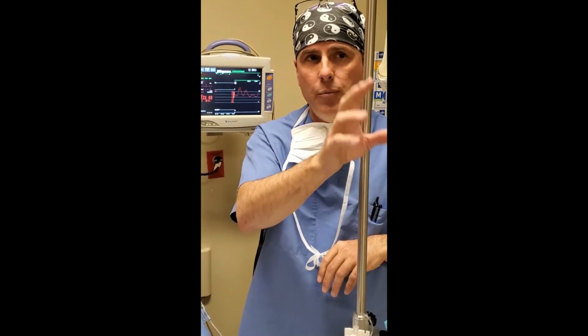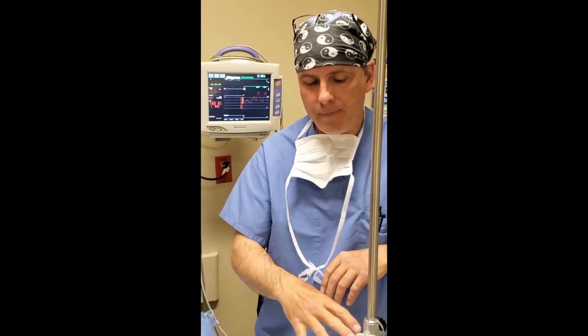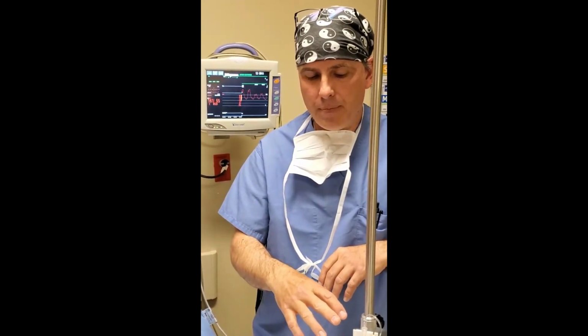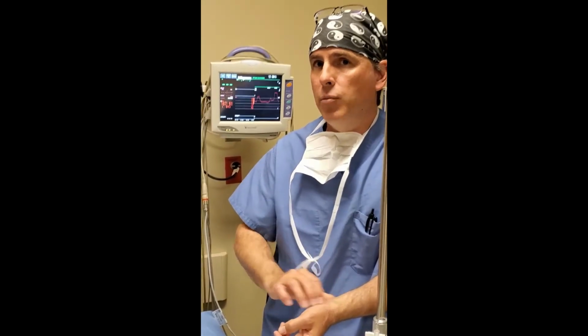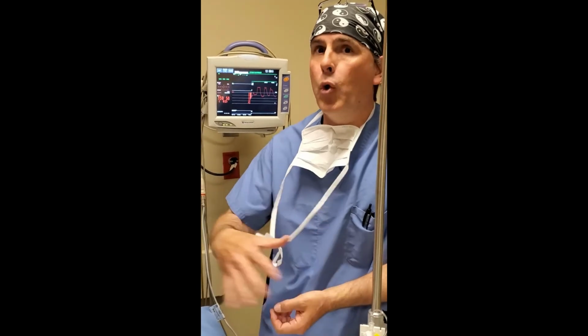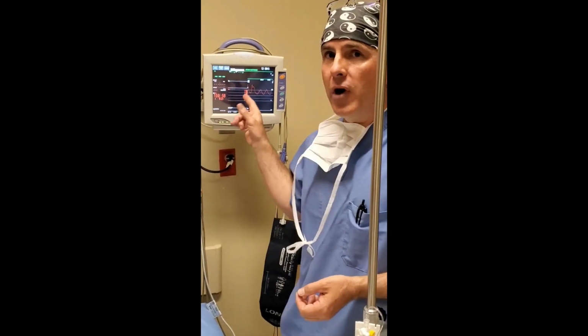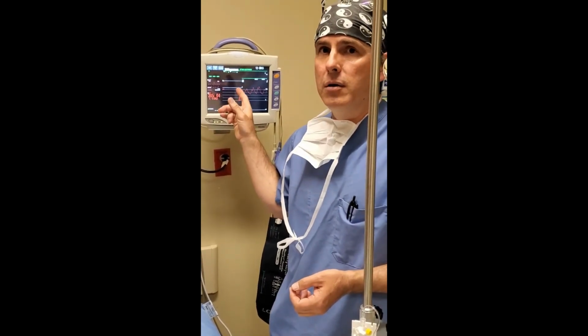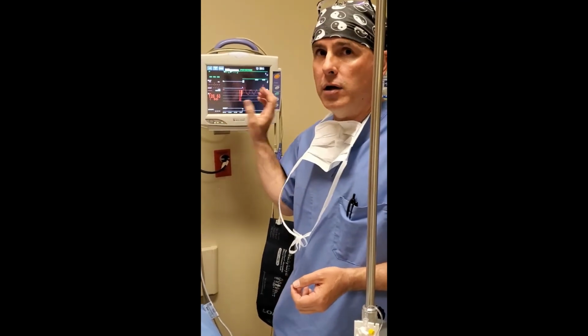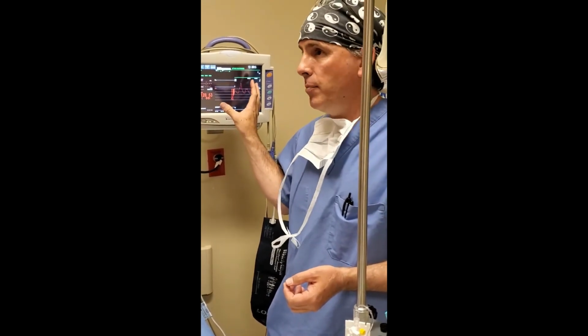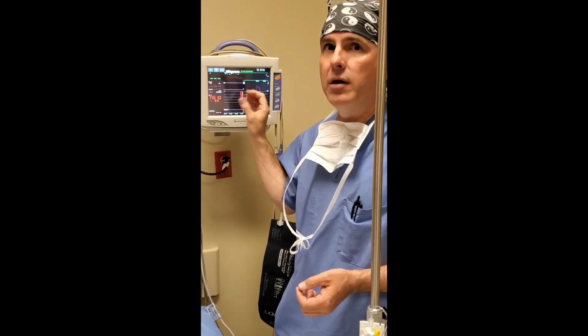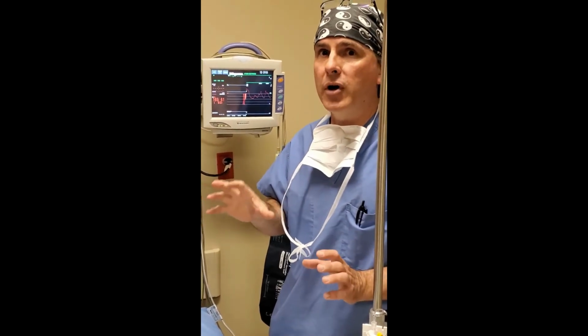We didn't put the pressure back on either. If this system disconnects and you have it in an artery, the blood is just going to pour out on the floor. If your alarms are off, your patient can bleed out. If your alarms are on, it'll alarm, and it should be a high-grade alarm, like an attention getter, like VFib or something, that gets your attention and says there's a problem here, come look now.